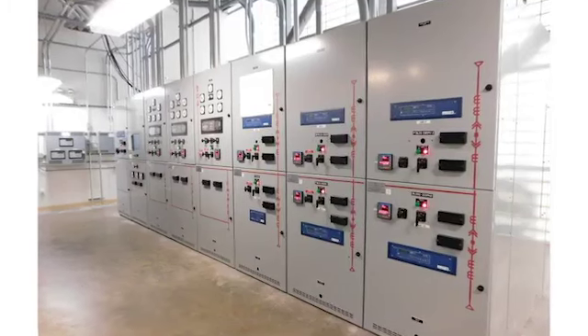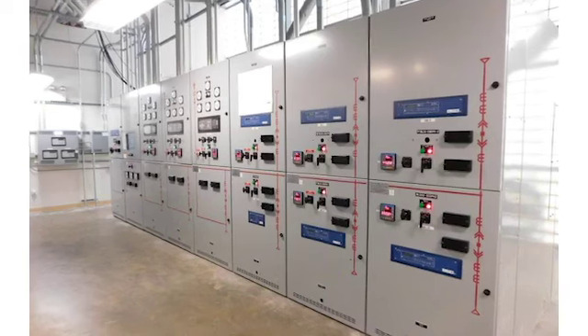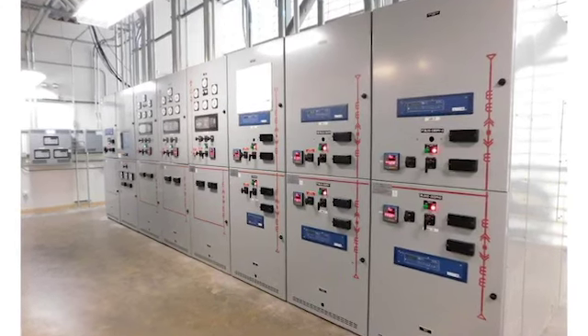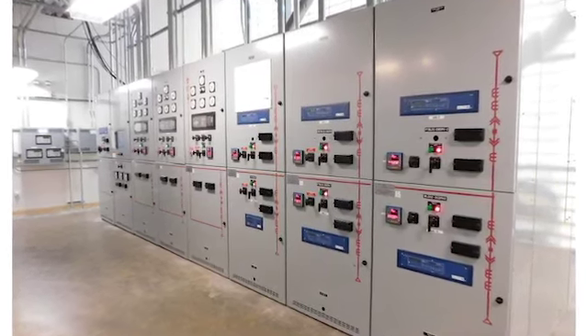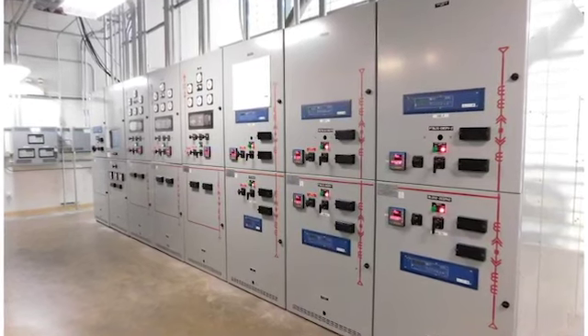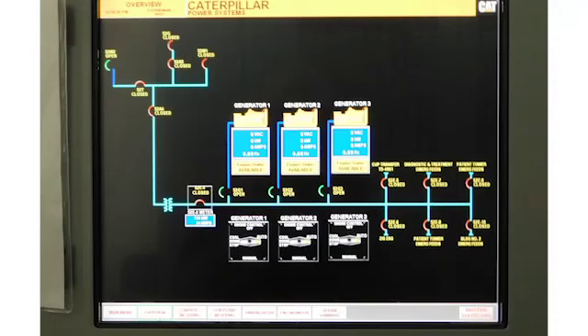Moving into the emergency substation, again, we have a dedicated emergency substation. We have three 2 megawatt emergency diesel generators. Their main breakers are right here on that bus. And again, they're managed by the CAT ISO control system, which through Modbus is monitored by the main plant control system. And we can dispatch and control the operation of the diesel plant from the control room.